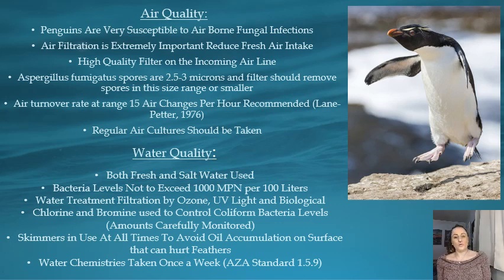Air quality and water quality are very important. Penguins are susceptible to fungal infections, so air filtration is extremely important. You need a high quality air filter. Aspergillus fumigatus spores are 2.5 to 3 microns, so we need filters that remove spores in that size range or smaller. We all got educated on that during COVID, so you can understand it's kind of the same thing. Air turnover rate at 15 air changes per hour is recommended, along with regular air cultures.